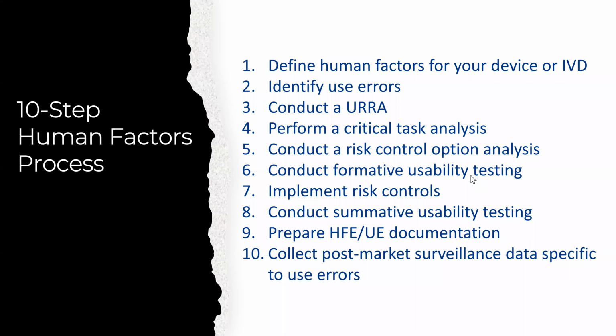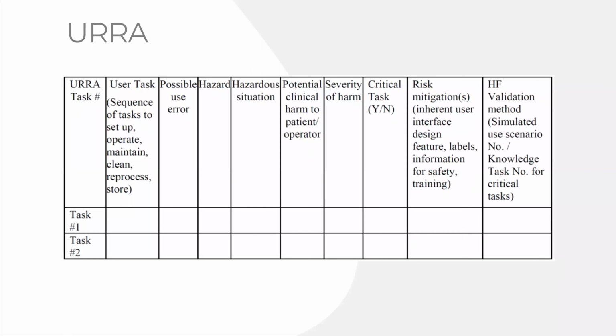The next step, you're going to want to create a URRA, or perform a use-related risk analysis. So I'm going to share my screen again. And here's an example that the FDA provided in deficiency letters showing what they expect for a use-related risk analysis. In the second column, what they're looking for you to do is list all the sequences of operation of your device, everything from storage to disposal, everything. Don't forget a step. And then from there, you identify the use errors that are possible for each of those steps. And not every step has a use error that's associated with it.